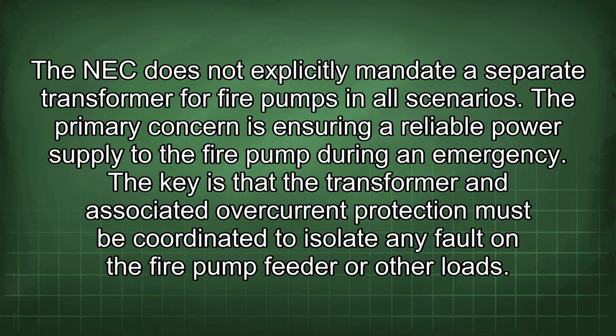The NEC does not explicitly mandate a separate transformer for fire pumps in all scenarios. The primary concern is ensuring a reliable power supply to the fire pump during an emergency. The key is that the transformer and associated overcurrent protection must be coordinated to isolate any fault on the fire pump feeder or other loads.